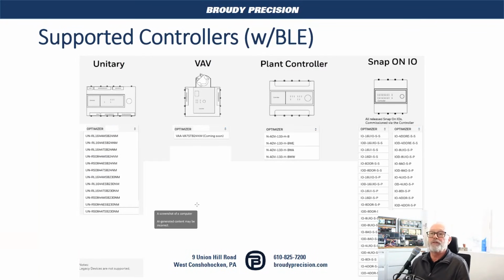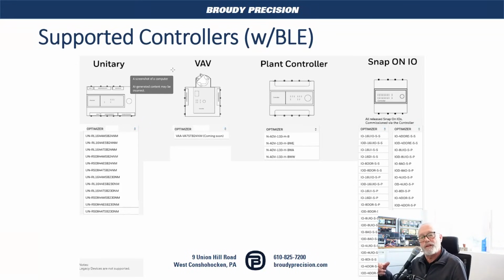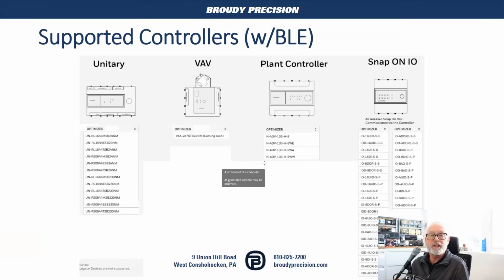The app supports the following: the unitary controller, any of the unitary controllers that are Bluetooth. One thing I should point out is you want to make sure you're at the latest firmware versions. The VAV controller, with a future firmware not yet released, will be available for this app as well. And if you have a Bluetooth model of the Optimizer Advanced controller, you'll be able to use this tool to work with the I/O on your panel bus I/O for the plant controller.